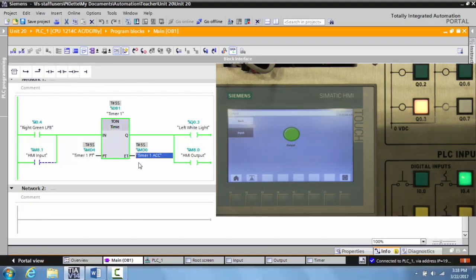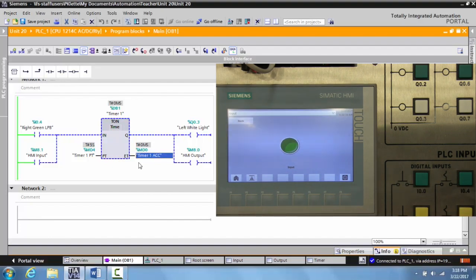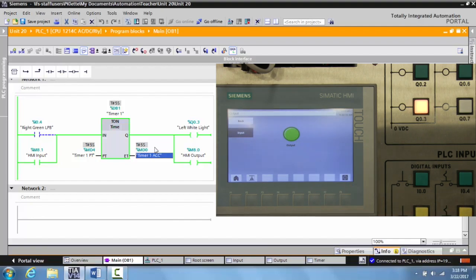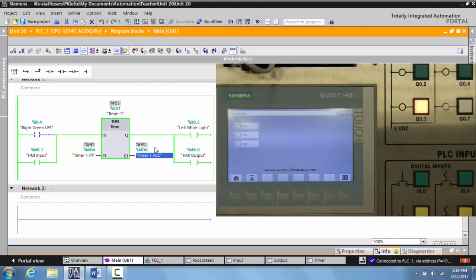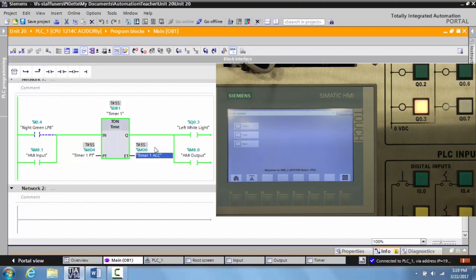If I deactivate the latch push button, the light goes off. Activate it again – five seconds later the accumulated timer reaches its preset value, the light comes on, and the HMI output is activated. I can go back to the root screen, go to inputs, activate the latching push button, and the timer is timing. At five seconds the white light comes on, and going back to outputs, that output is activated too. This is a very simple example of using multiple screens in your PLC program. Each screen can be used for data collection, on/off functions, monitor functions, controlling timers, counters, and more. This was unit 20 in the TII Technical Education Systems Trainer set up for Siemens PLCs and HMIs. Thanks for watching.